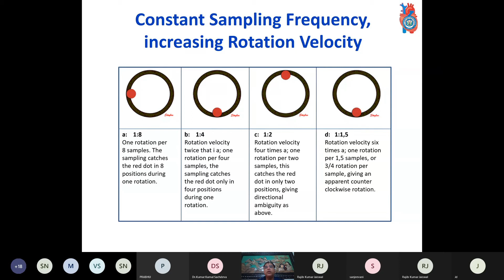If we further increase the speed, what happens? Analyzing the maximum velocity measured by the pulse wave, it is half of the pulse repetition frequency. We should not keep more than half of the pulse repetition frequency whenever we are doing a Doppler assessment, so that the analyzing velocity is within the range of our human eyes perception. If the Doppler velocity exceeds this, then the pulse wave is displayed in the opposite direction. If the velocity increases, then we see the velocity on the other side of the baseline.